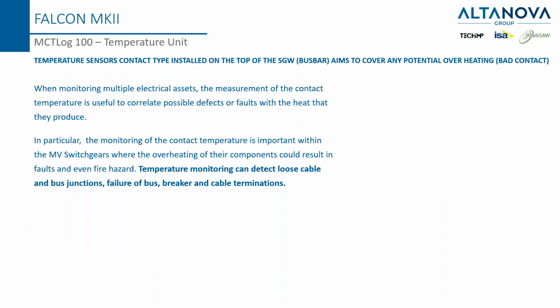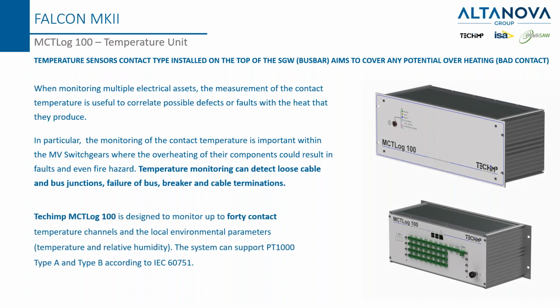Regarding the temperature monitoring features of the Falcon Mark II, there is another 19 inch rack, to be hosted in the same enclosure, that can be connected to up to 40 contact temperature channels. Temperature sensors. This actually has a consistency with the Falcon unit that can monitor up to 40 partial discharge channels. So they are designed to be put together in the same cabinet.